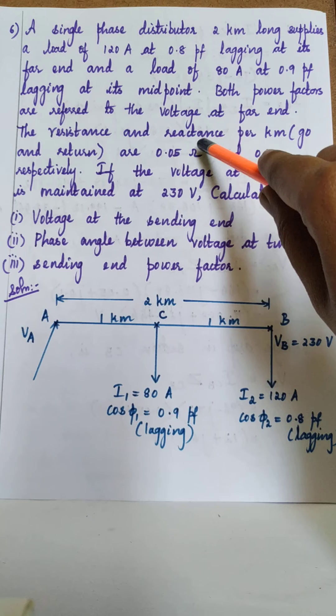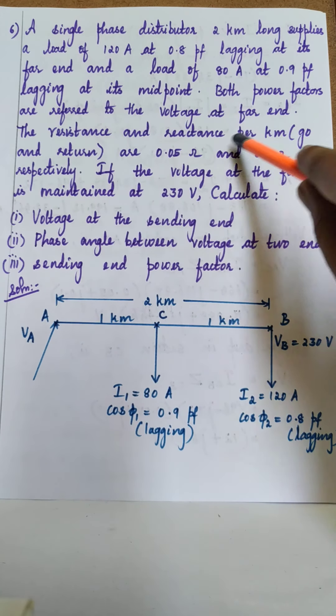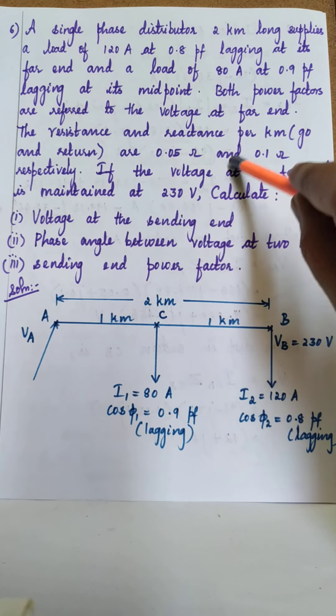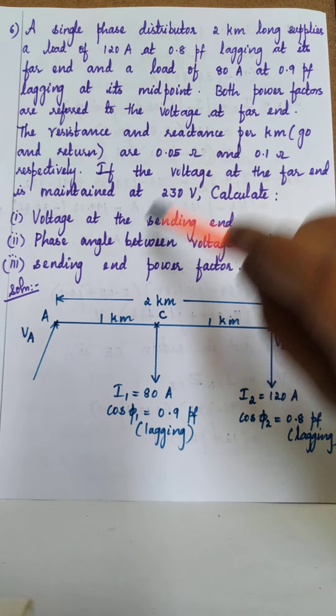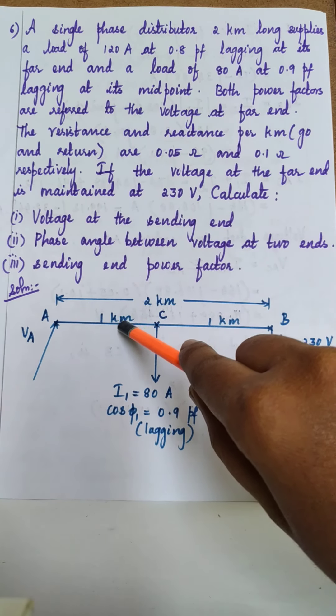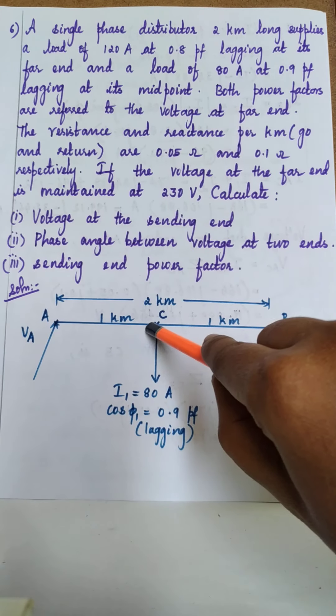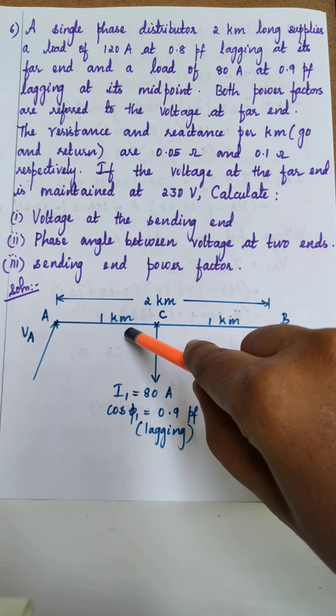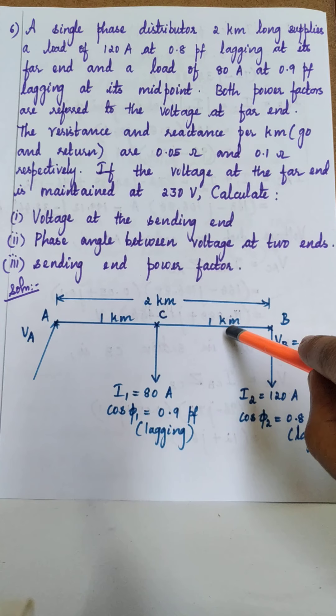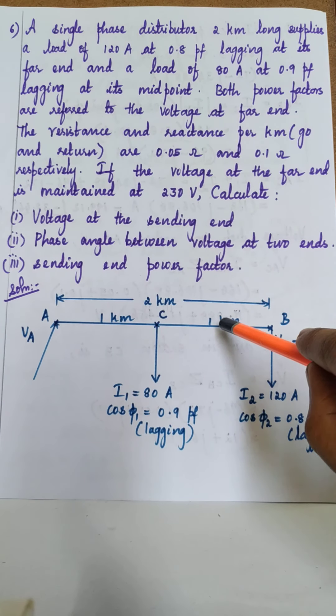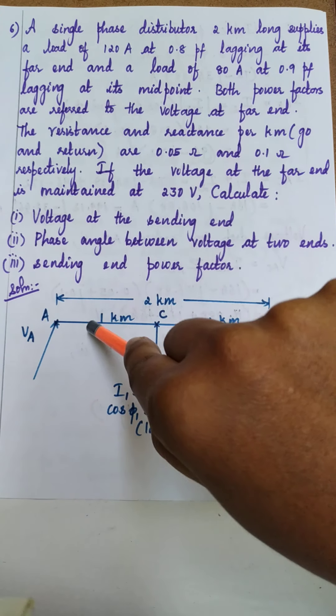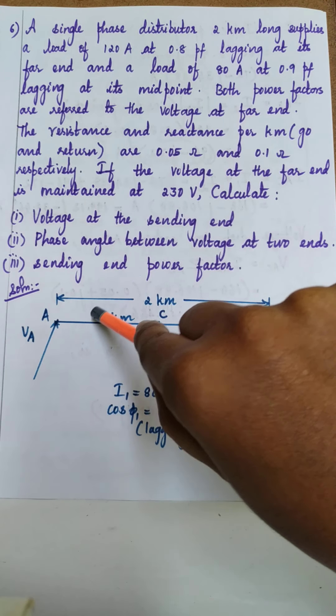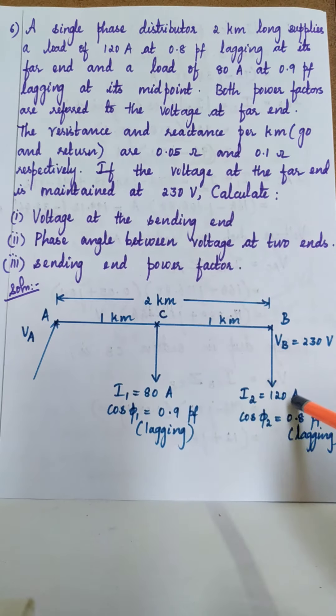The resistance and reactance per kilometer is 0.05 + j0.1, so since section AC is 1 km, ZAC = 0.05 + j0.1. ZCB is also 0.05 + j0.1. The current IAC is the sending end current, which equals I1 plus I2.